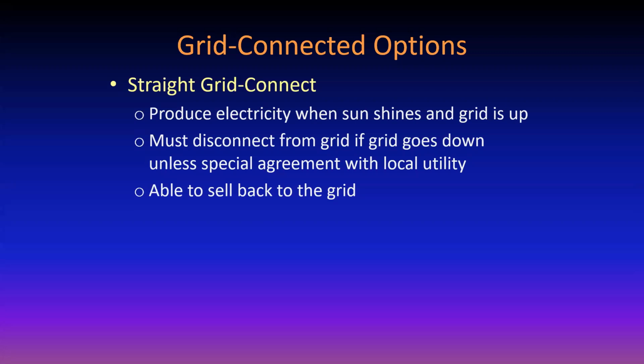Now, there's always an exception. IEEE 1547-2000 now provides for an agreement to be signed with the utility that the utility can keep your system running, because a PV system can actually help the utility in the afternoon by generating electricity when the utility needs it the most. And if the utility is getting overloaded to the extent that their frequency drops where your system might go off, that would actually exacerbate the problem. So the utility would like to be able to keep the system up as long as their grid is intact. So that's just a new change as of this year. They've been talking about it for a while, but it went into effect this year.